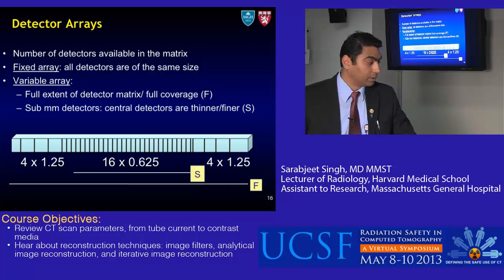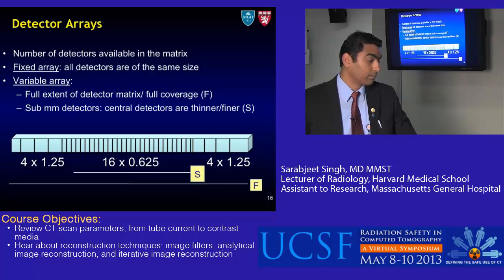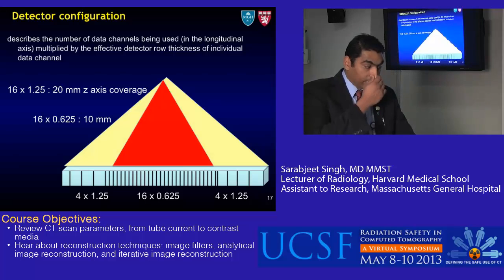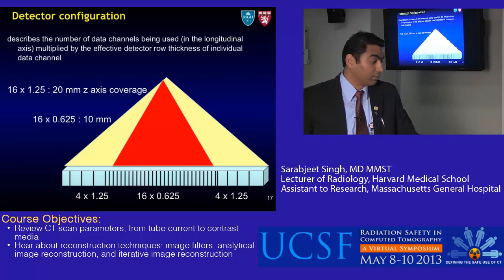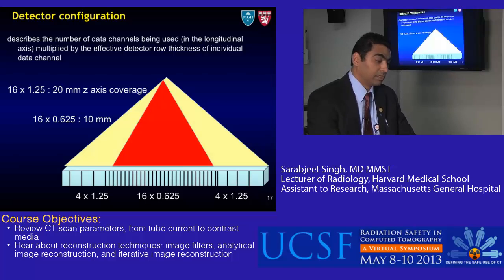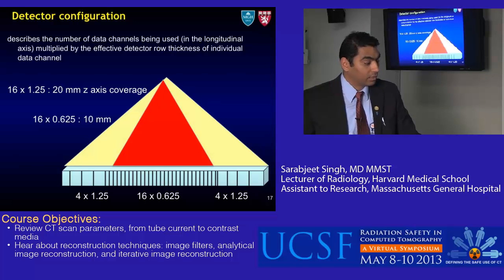Next we have detector arrays, which is the number of detectors available in the matrix. It can be a fixed type, where all detectors are the same size, or variable. In variable types, there is the full extent of the detector matrix (full coverage) and sub-millimeter detectors, which are central detectors that are thinner or finer. Detector configuration describes the number of data channels used in the longitudinal axis multiplied by the effective detector thickness of each data channel. For example, 16 × 1.25 mm gives 20 mm z-axis coverage, and 16 × 0.625 mm gives 10 mm z-axis coverage.